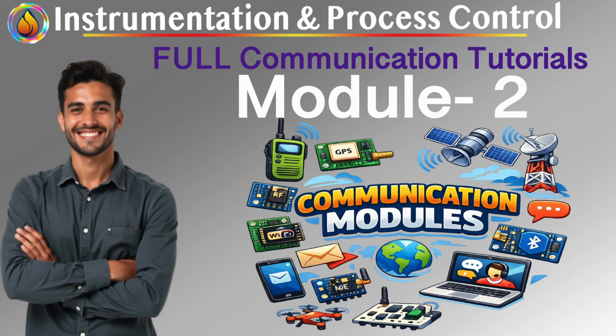DTE and DCE. The first trap you fall into, RS232 was never designed for industrial control. That's not an insult, it's historical fact. Its original purpose was very specific. Communication between data terminal equipment, DTE, and data circuit terminating equipment, DCE. Think computers talking to modems. Hence this strange wiring logic. DTE transmits on one pin, DCE transmits on the opposite pin. Ground is shared and assumed stable. On your desk, with one PC, one device, one power source, one earth reference, this assumption holds. In a plant, it quietly collapses.